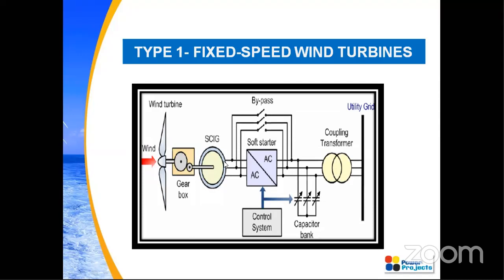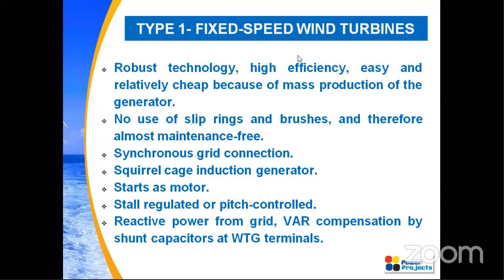And we will have a soft starter, and it is directly connected with the grid. The reliability will be high, and it is usually stall regulated. I told you about stall regulation when I talked about the lift force and drag force. So these types of turbines are usually stall regulated, and very rarely pitch regulated. The overall efficiency will be very low. In recent days we are not using this much, but they were installed a few years back, so it is still in operation. So we have to know about this too. Here are some points about the fixed speed wind turbines. As I told, it requires reactive power, so VAR compensation is necessary.